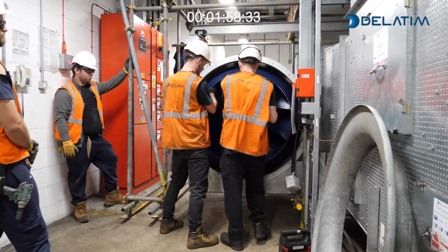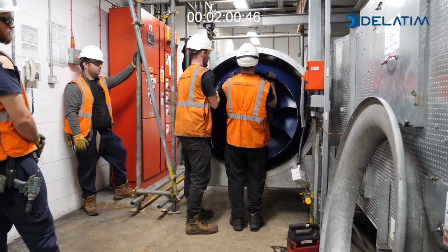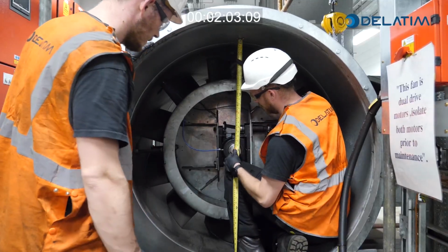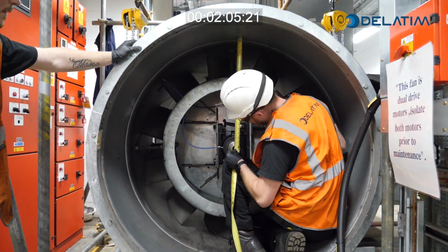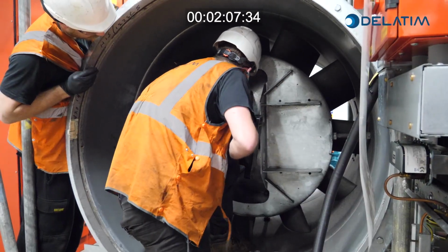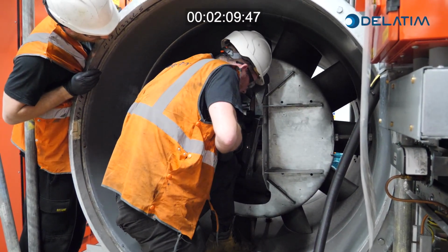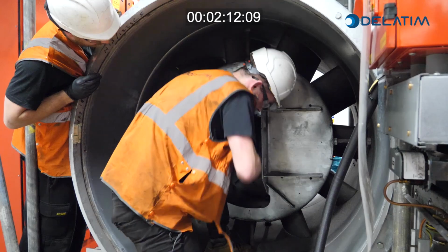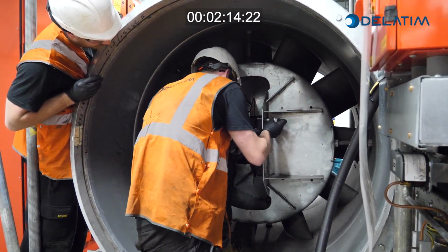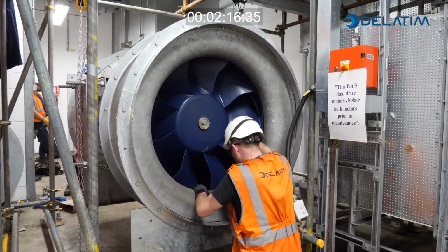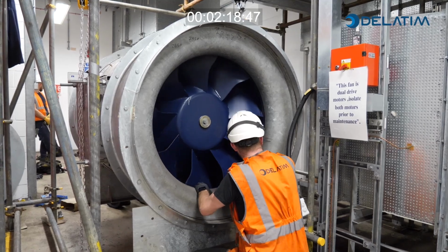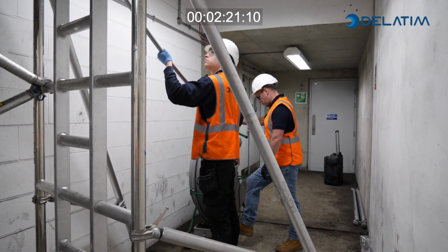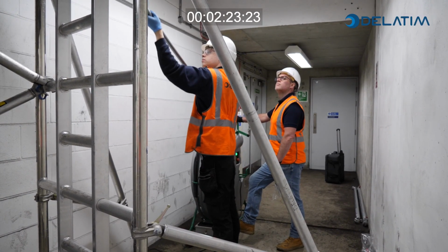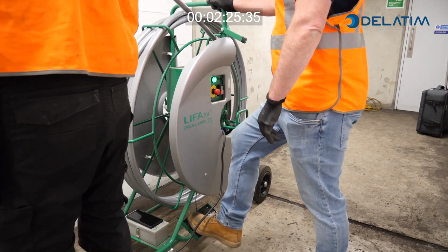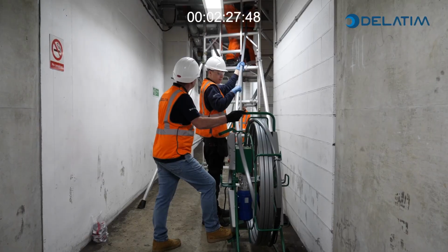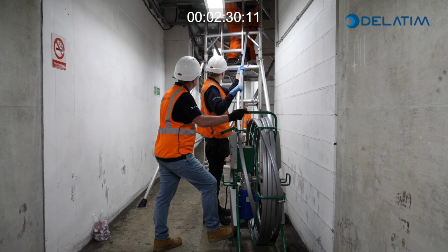Delatim employed specialist contractor Browning Electric to undertake the associated works for the supply fan and motor upgrades. The scope included the replacement of the fan shaft bearings, the fan belts, bushes and pulleys, the replacement of all flexible duct connectors and the replacement of all anti-vibration mounts. The replacement of all motors for new modern day equivalents, with the exception of 3 inline motor systems that required a rewind to refurbish the existing.